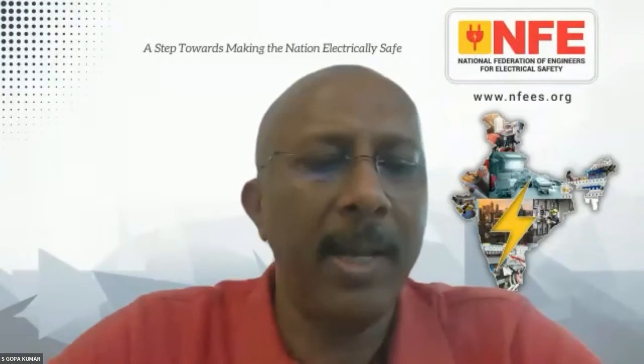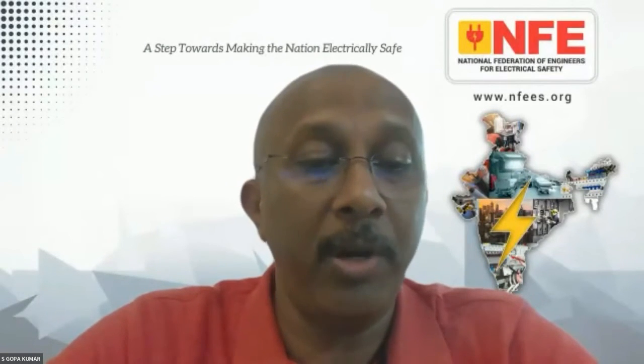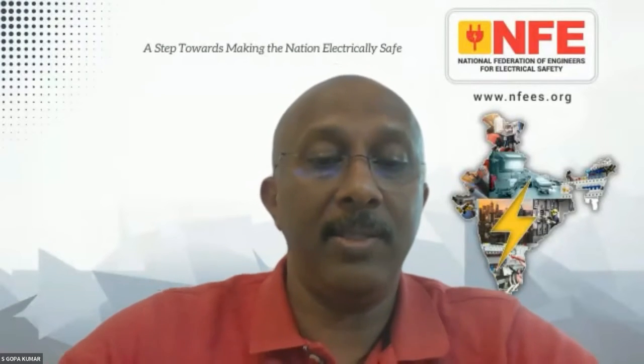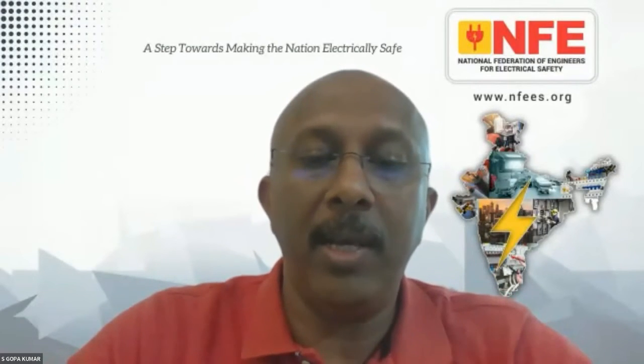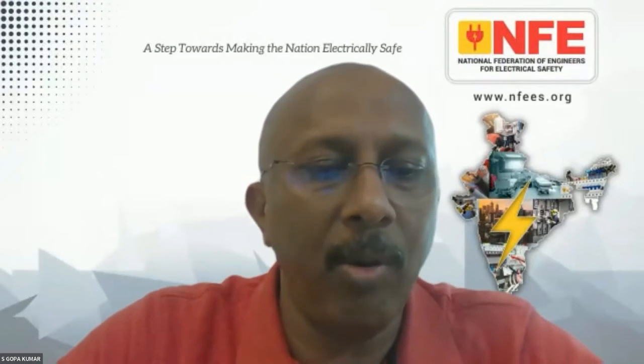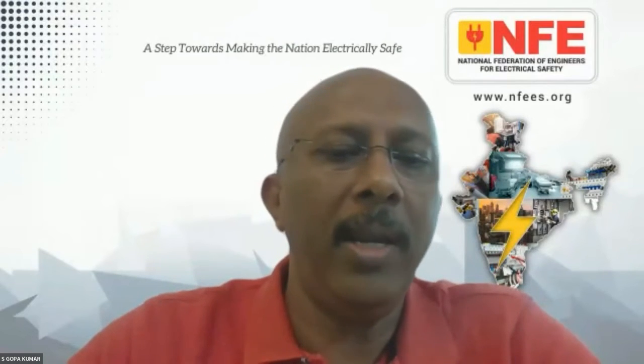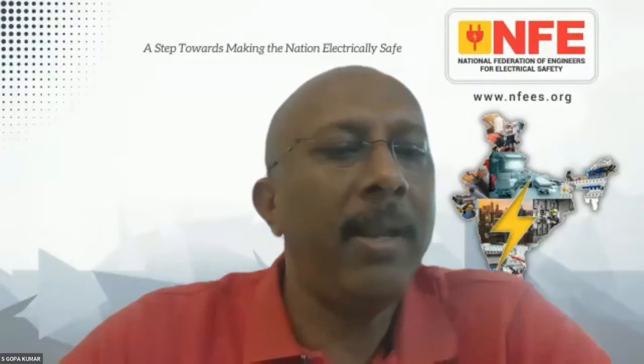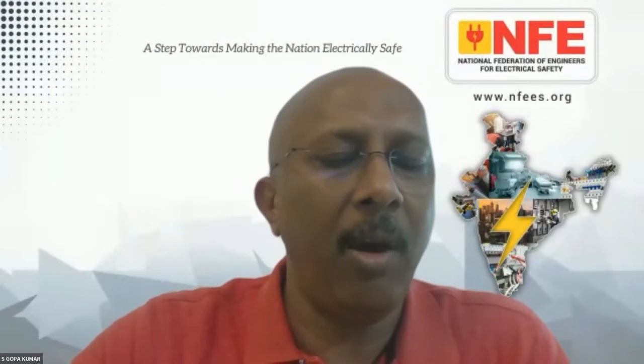I am so sorry to make a comment here. Whatever is written in some of the OISD standards is really big foolishness. Sorry to use the word foolishness. In the sense, if you wanted to see, I can show you the regulations as well. The OISD standards say electronic equipment needs a separate earthing of 1 ohm, lightning protection a separate earthing of 7 ohm, transformer neutral a separate earthing of 2 ohm. I don't know from where such foolish ideas came into a very important rule, which is followed all over India in the oil and gas sector.